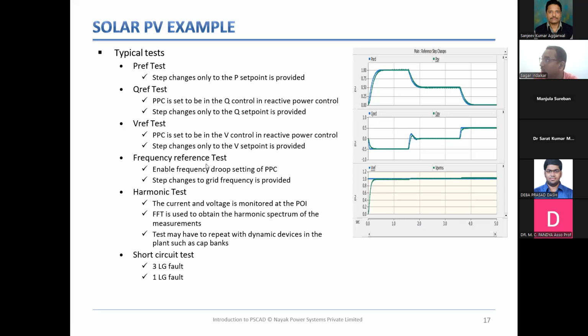Then you have your frequency reference test. In the frequency reference test, what you do is you enable the frequency droop settings of the PPC, and then you create a disturbance in the grid. So you reduce or increase the grid frequency. Let's say from 50, you will go to 50.5, or you go to 49.8, and then you will check whether the PPC is ordering, and the overall plant is ordering, grid support or not. So let's say if the frequency falls below 50, then you should inject active power. If the frequency goes above 50, then you should reduce active power.